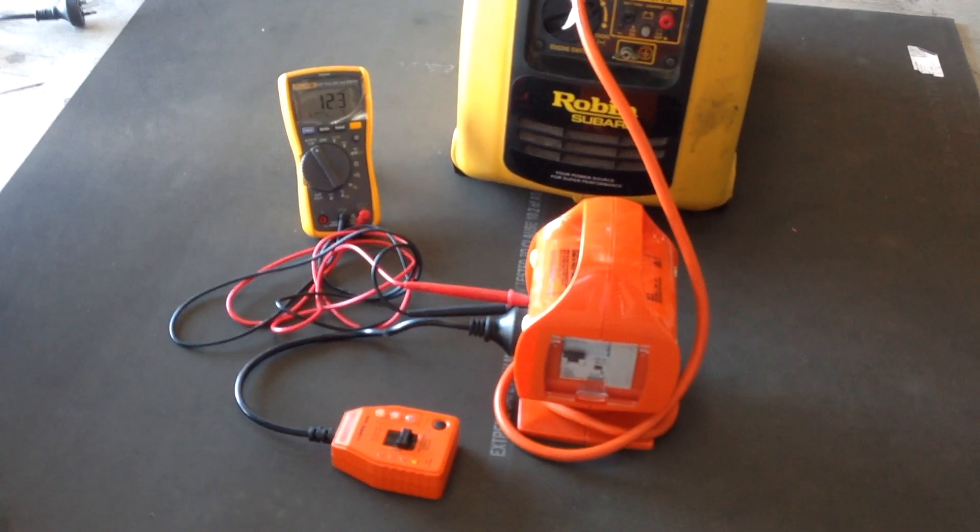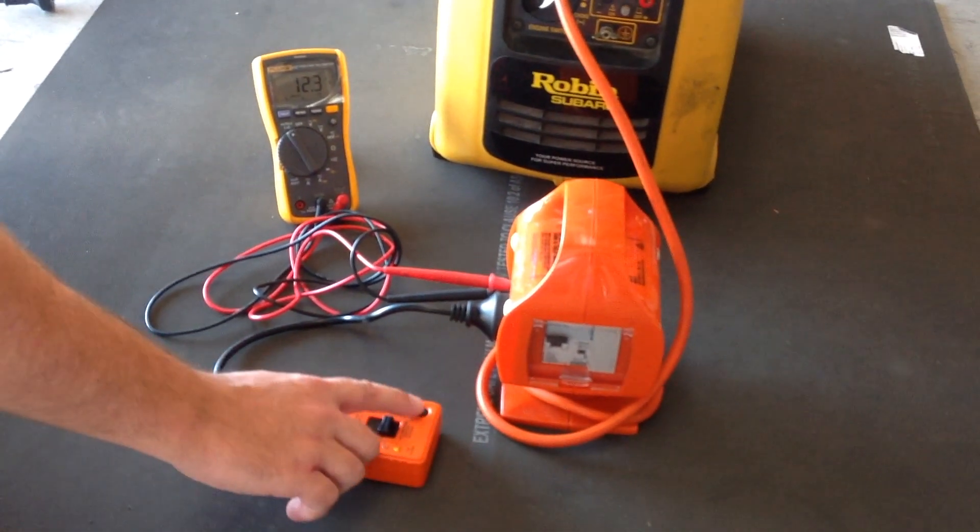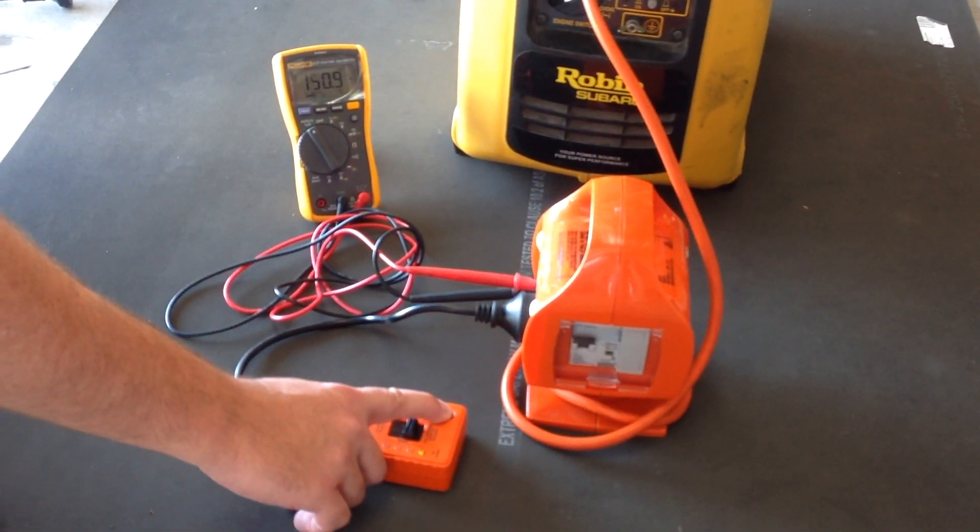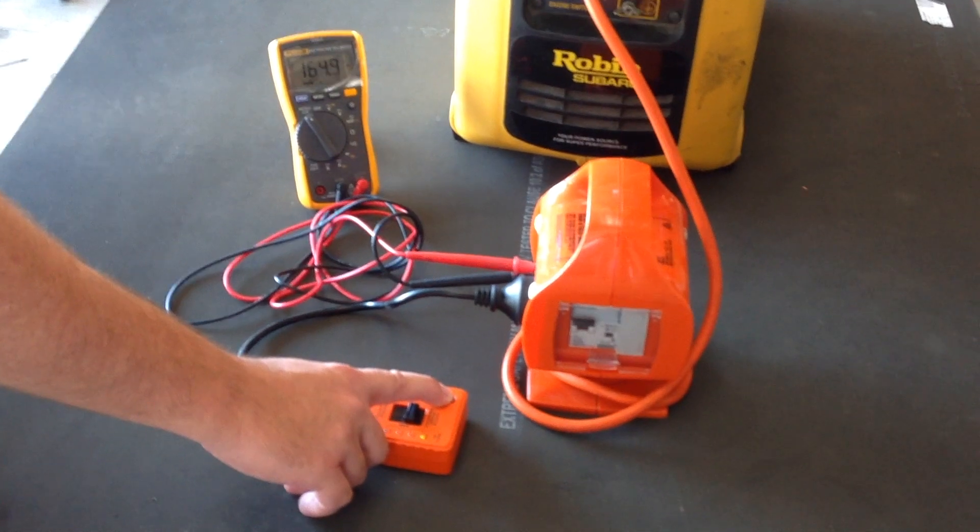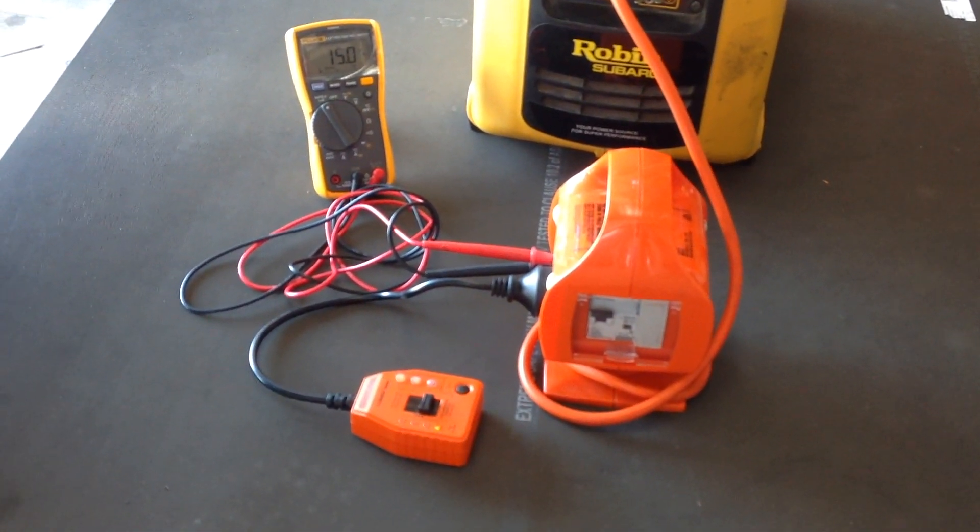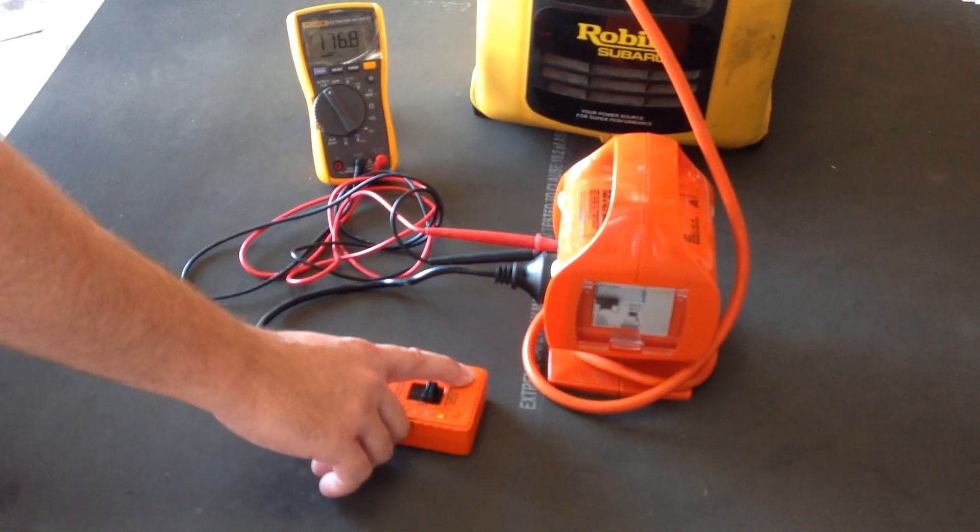Connecting the power board to a generator and pressing the RCD tester button, we will create a fault and we will see that the RCD will not trip as there is no current flow in the earth path.